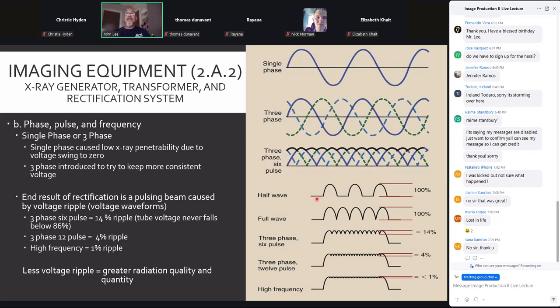Without any rectification, again, X-ray tubes don't operate on AC. So if we were to take AC, non-rectified, and try to put it through a system, we're going to produce X-rays only half the time. Because on that negative half, electrons can't go the other direction from anode to cathode. So half the time the machine's working. That's what we call half-wave rectification. If you put two rectifiers in a single-phase system, you can achieve full-wave rectification properly. Improper way is not to put any rectifiers at all and just let the X-ray tube do the work.